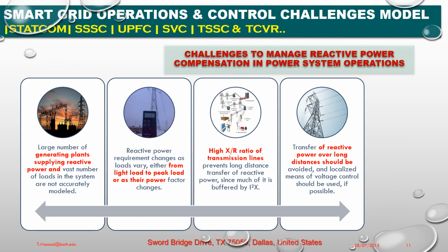Challenges to manage reactive power compensation in power system operation. Number one, the large number of generating power plants supplying reactive power and the vast number of loads in the system are not accurately modeled. That is first. Number two, reactive power requirement changes as loads vary, either from light load to peak load or as their power factor changes. That is the second challenge. Number three, the high X/R ratio of transmission lines prevents long distance transfer of reactive power since much of it is consumed by I squared X. So that is another big challenge.